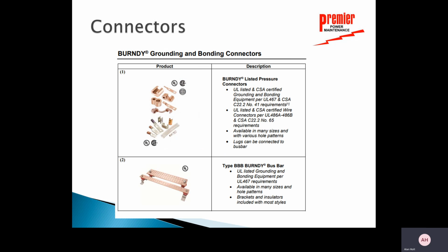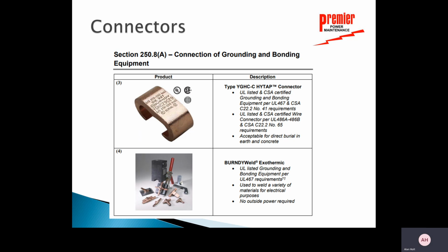So if I look at the various connectors, I can see things. One of the big suppliers is Burndy, obviously. But I can see the various products. I can see, again, those compression fittings, all those are compression fittings. I can see bus bars that I would see on the back of possibly relay panels. So that would be a place for me to connect my grounds to. I can see a HYTAP connector here. Again, that's a crimp type connector.